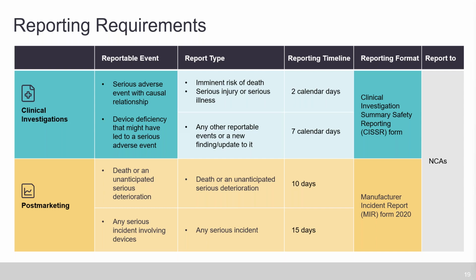The reporting format is very important to know for clinical investigations. There is a clinical investigation summary safety reporting form, or the CISSR form, which is currently used to report to the NCAs, the national competent authorities. On the post-marketing side, the timelines are 10 and 15 calendar days, and here we use the manufacturer incident report form, the MIR form, 2020.